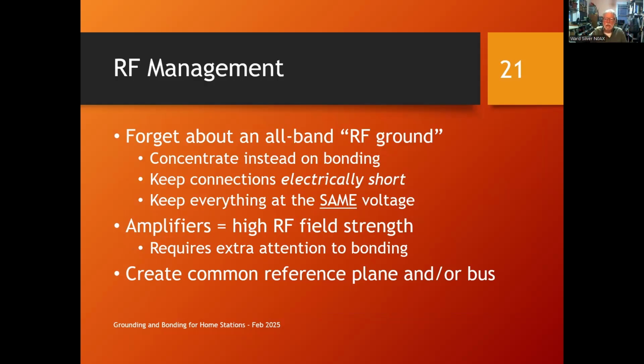It's not going to happen. Concentrate instead on bonding all your stuff together. Boy, I'm doing this a lot, aren't I? So that everything goes up and down together, whether it's AC or lightning or RF from your transmitted signal. You want it all going up and down together so it doesn't cause current flow between these pieces of equipment, which causes RFI and all kinds of other problems. You want all these connections between these pieces of equipment to be electrically short. So short, direct wires, and it keeps everything at the same voltage.